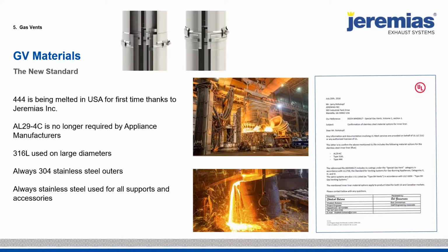Now, something about the materials on our gas vents, as well as the original conical and the flange system we talked about at the very beginning. I did mention 444. It is being melted for the first time in the States, thanks to Jeremias. I should mention that AL29-4C is no longer the requirement by the appliance manufacturers. All the IOMs say AL29-4C or UL 1738 equivalent. We actually use 316 like everyone else does on large diameters above 36 inch.